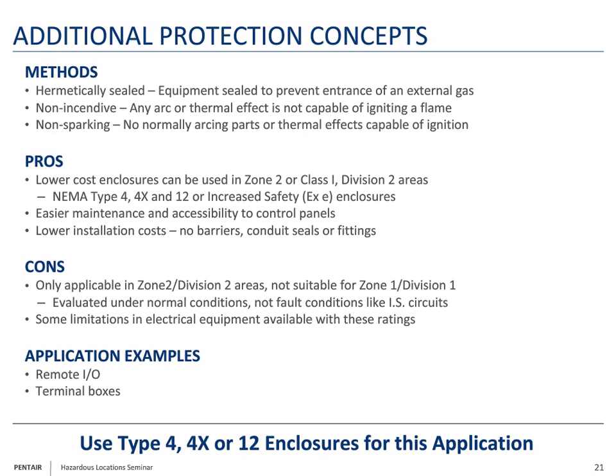The con is it's only applicable to Zone 2, Division 2 areas. It's not suitable for Zone 1 or Division 1 areas. And there are also some limitations on what electrical equipment is available with these ratings, so you have to investigate that. Typically, you see remote I/O and terminal boxes. There are some PLCs that have Class 1 Division 2 certifications on them, or Zone 2 certifications. So it's something to be aware of.